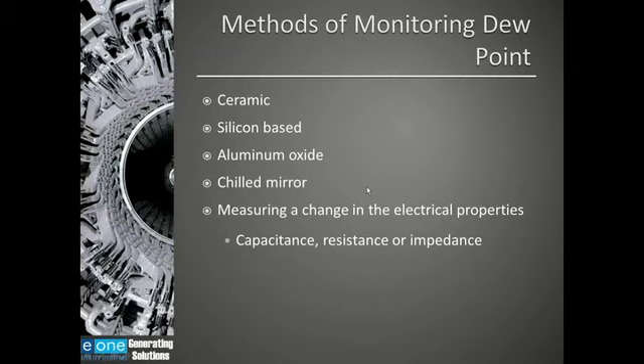How do we monitor dew point? Well, here's a list of some sensors that can be used to monitor dew point. Ceramic sensor, silicon-based sensor, aluminum oxide. I don't believe that chilled mirrors have ever been used in hydrogen-cooled generators, but chilled mirrors are used to monitor dew point. All of these devices are measuring a change in an electrical property, whether that be capacitance, resistance, or impedance.